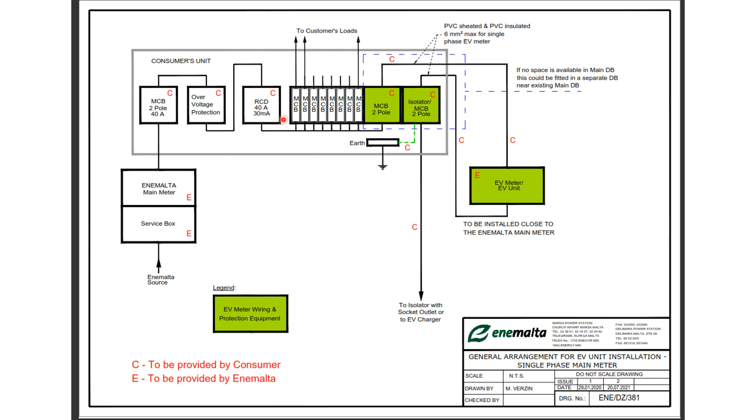It's very important that all final circuits are protected with this 30 milliamp RCD because anything which is slightly higher than 30 milliamps, typically around 50 milliamps, can cause injury. So all final circuits must be protected with a maximum of 30 milliamp RCD.